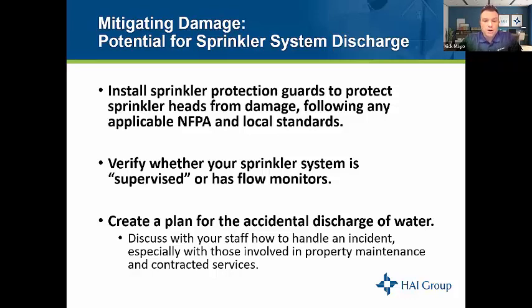We want to verify whether our sprinkler system is supervised or has flow monitors. So the majority of sprinkler systems within buildings are going to be supervised. And what supervised means is there will be a flow switch within that sprinkler system that when activated, that switch will communicate with the fire alarm system. The fire alarm system will give an alert to a central station dispatch or your fire department dispatch.